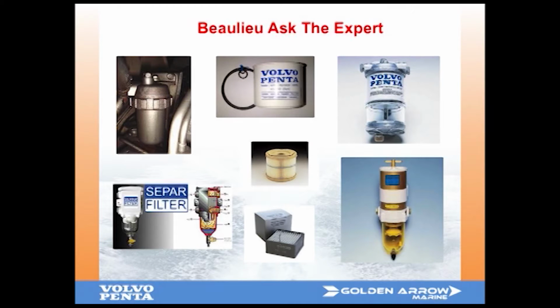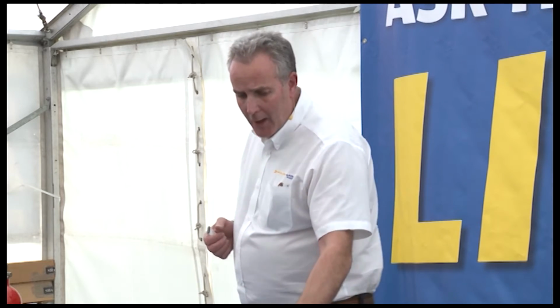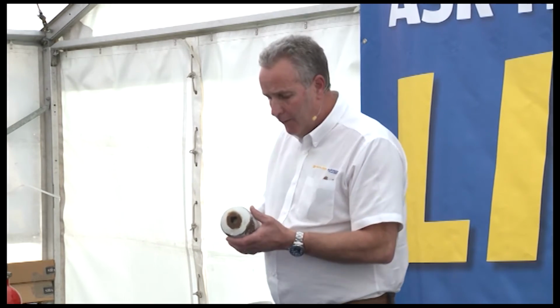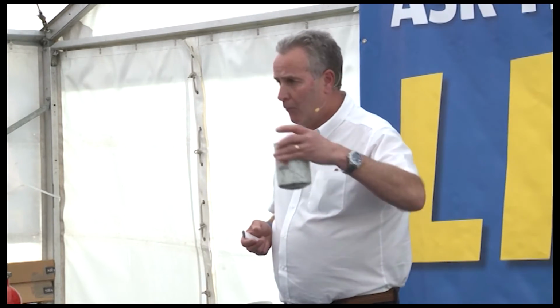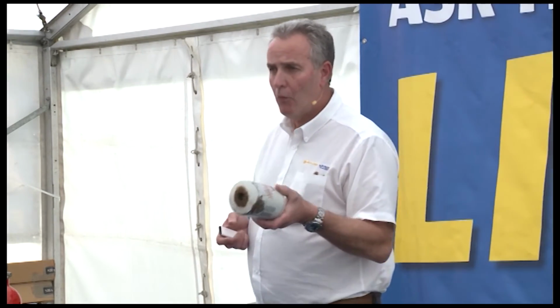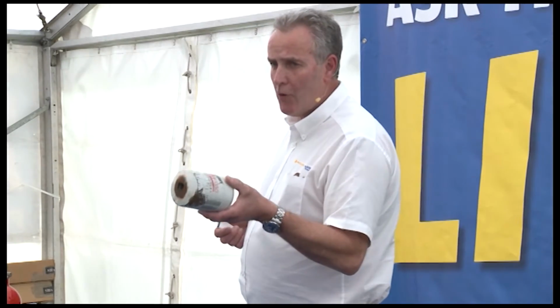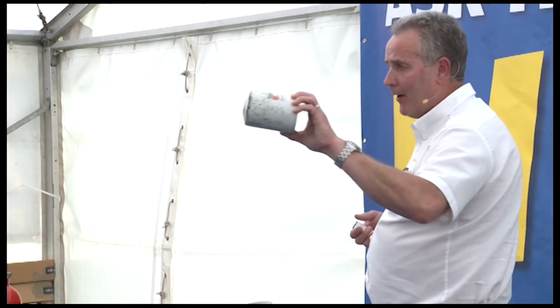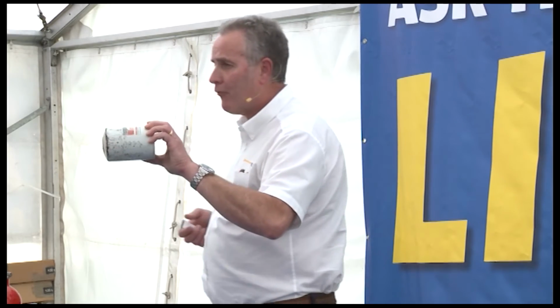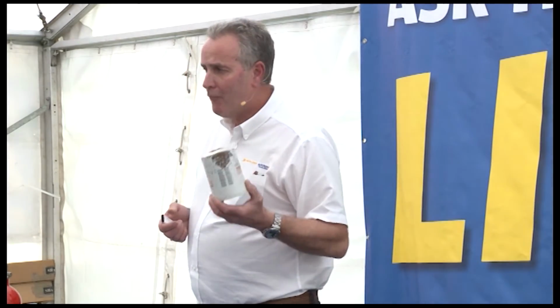At least you've got a visual, you can see inside the filter if you've got any fuel bug, which is quite black and gooey, or any water, and at least then you can drain it off. Because with this type of pre-filter, if you get water in it, that causes corrosion inside the filter, and it corrodes from the inside out. So you've got to be very careful.